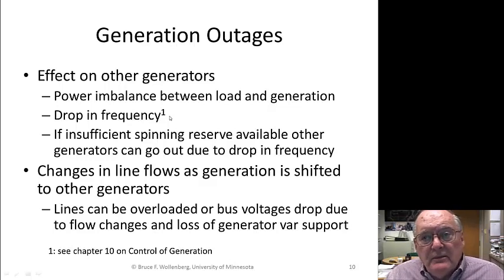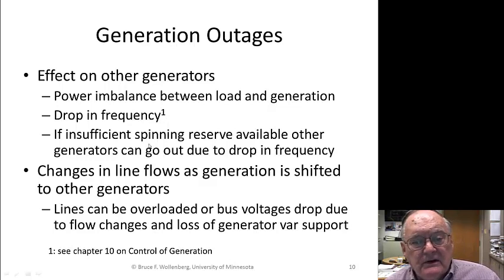They're going to hit their upper limit, and they can't make up for the total generation that you've lost. And now your frequency is just going to start going down, and the system will black out. The generators will go off one by one, and the system will black out. So we have to make sure, we have to do a spinning reserve test and monitor that. So that's one of the what-ifs.